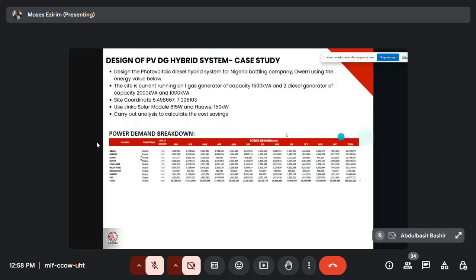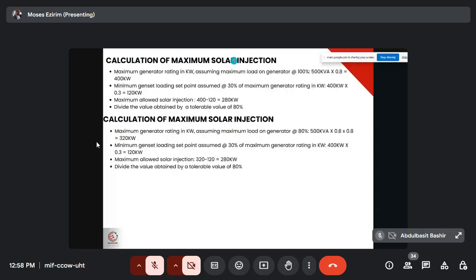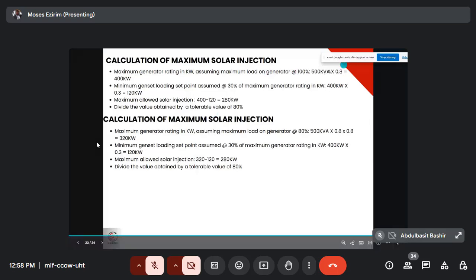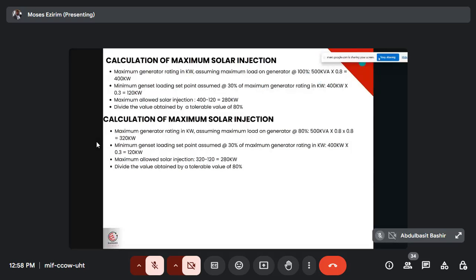Now let's see how to calculate our solar capacity. Maximum generator rating in kilowatt, assuming the maximum generator is 100%. You can see the maximum generator capacity is 400. Now the minimum genset loading at 30% is 120. So this is the base load. Now if I have the base load, how do I size my solar capacity?